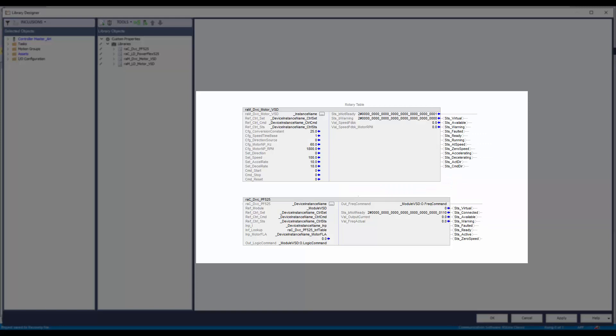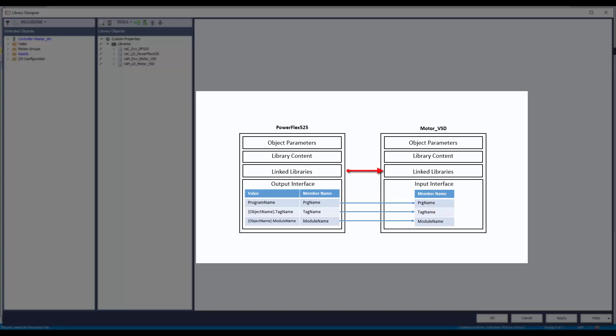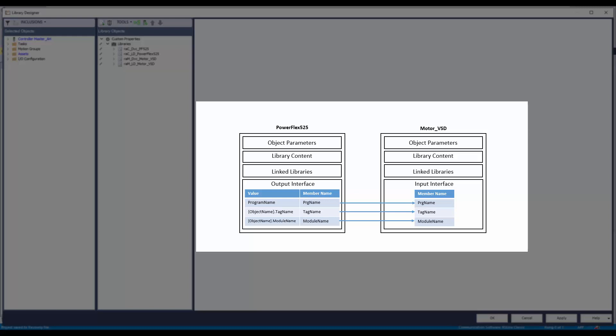For the demo, I have PowerFlex 525 and Motor VSD library objects. The Motor VSD belongs to the application layer code managing the operation of a motor like Start, Stop, Fault Reset, and Ramp. The PowerFlex 525 belongs to the device layer managing the physical hardware by issuing commands and references. Both these instructions are connected using control interface tags for setting, command, and status. While instantiating Motor VSD library in ACM, the PowerFlex 525 device object is instantiated as a linked library. The control interface tag names need to be passed from PowerFlex 525 to Motor VSD library using the output and input interfaces.